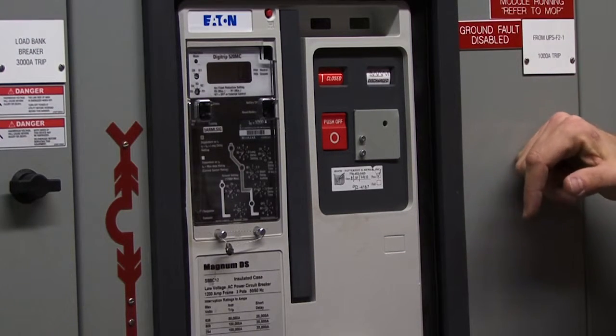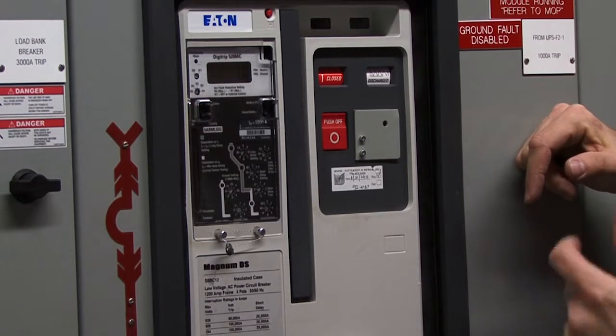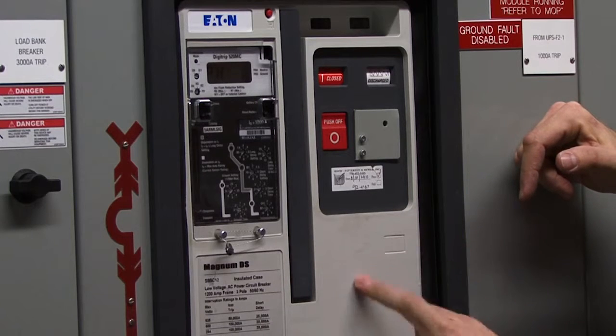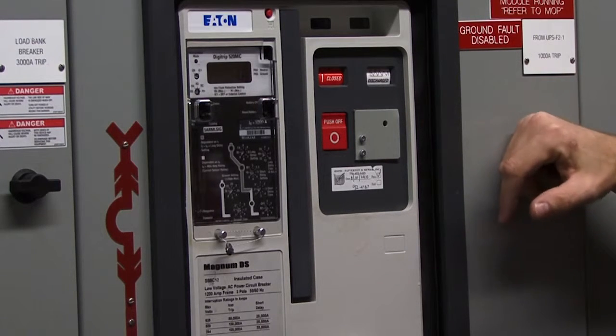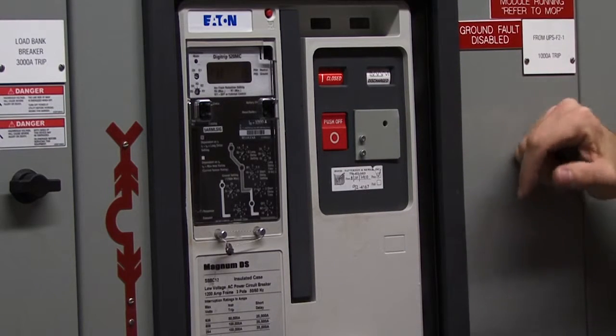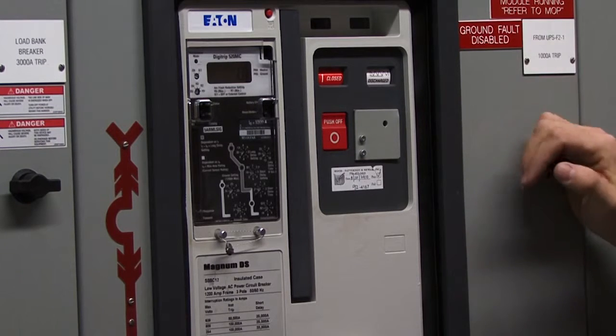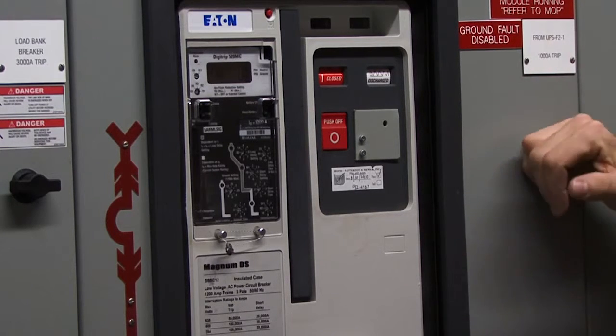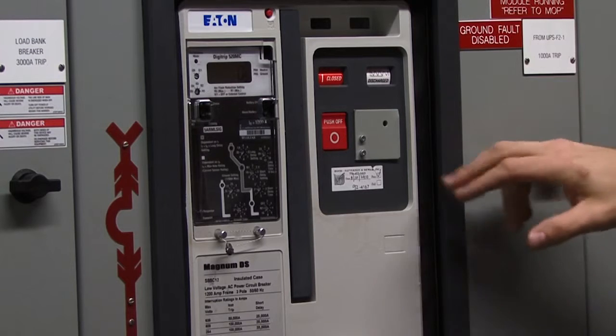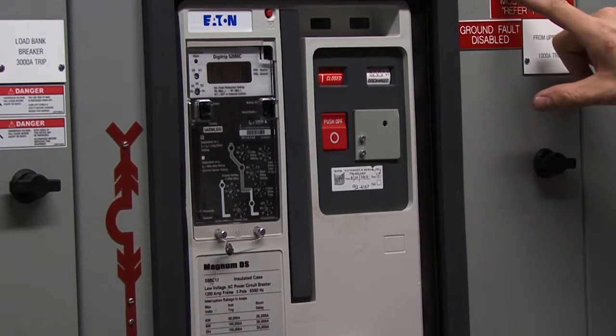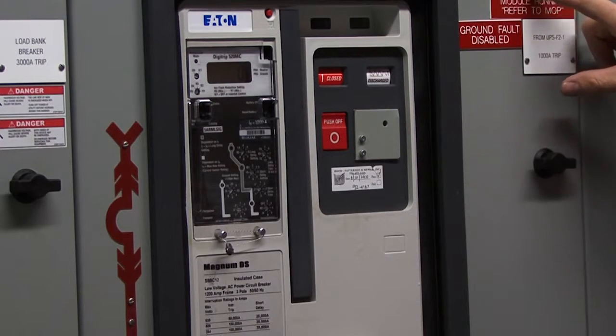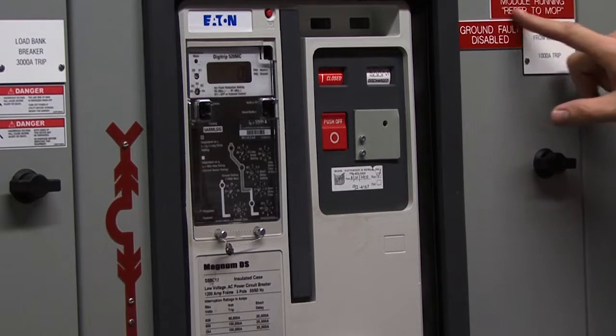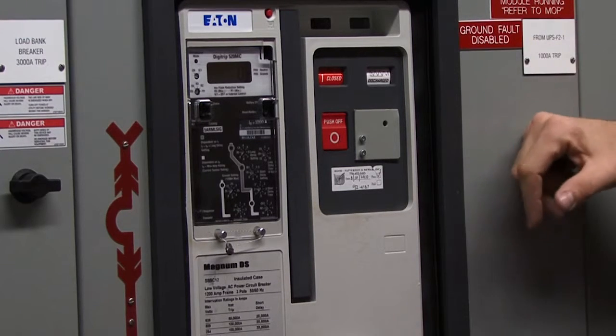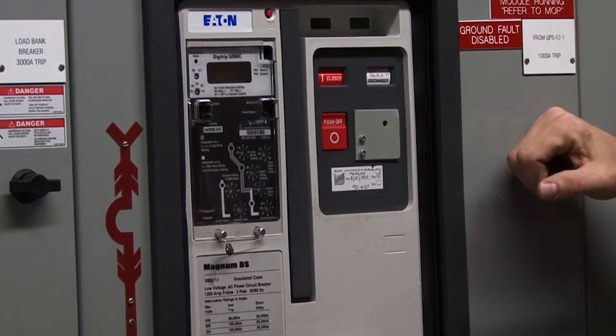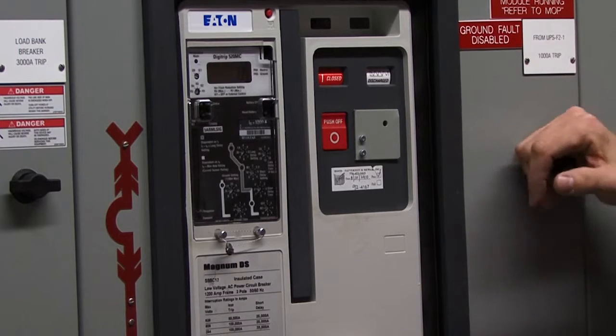So if you take a module that the other modules don't realize is there, and then you instantaneously add it to the system by closing this breaker, the system will not respond favorably. It may transfer to bypass, may cause some synchronization issues. So it should never be done. So that's why this plate is here. And then also there's a red label that says, do not close this breaker with associated module running, refer to MOP. MOP being the MOP written by QTS for operating this gear.